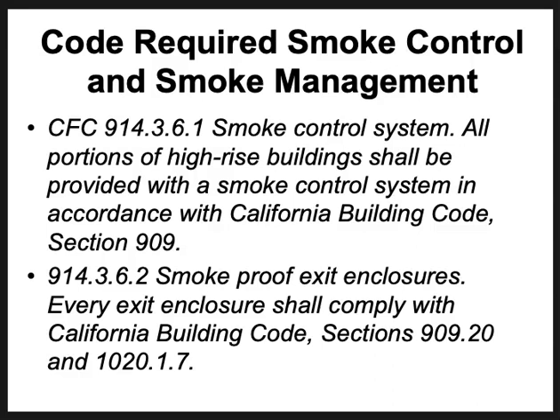Chapter 9 in the Fire Code and the Building Code are going to give us specifics. In 914.3.6, we're going to have the specific requirements that are going to say what and where, not the how, but all of the what. That it's going to say this is where it's required. So all portions of high-rise buildings have to be protected with smoke control systems. And smoke-proof exit enclosures, every exit enclosure has to have some kind of smoke protection as well. And what we're talking about is large stairwells in high-rises and things of that nature.